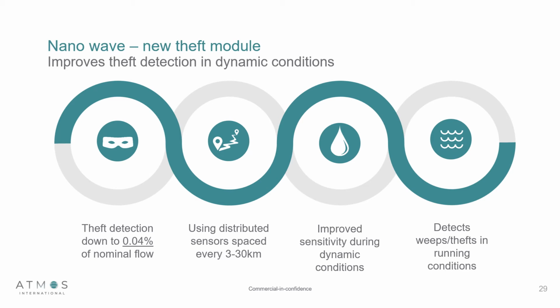So how does the Nano Wave module work? Well, it uses distributed sensors spaced every 3 to 30 kilometers, depending on the pipeline length. If you have a very, very short pipeline, for example, let's say 1 kilometer, then you would space them accordingly. From testing, we've been able to get theft detection down to 0.04% of the nominal flow. And we do this because we use longer filter lengths and cross-checking against all the pressure sensors along the pipeline. This module isn't interested in large leaks or ruptures. It's purely there to look for these slow openings of a potential theft event. It's also very good at detecting weeps as well, because weeps have a similar characteristic to thefts.